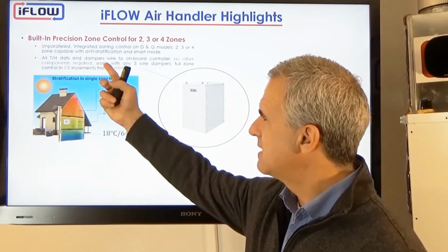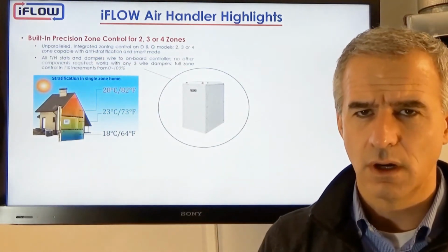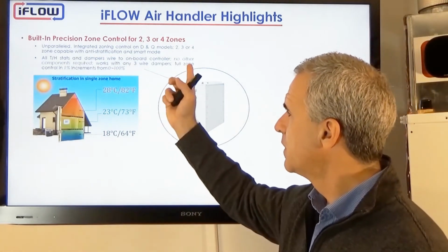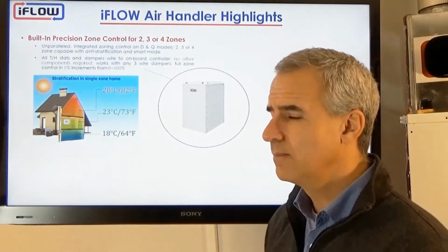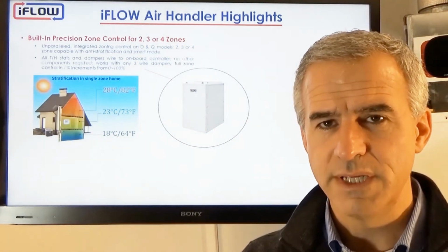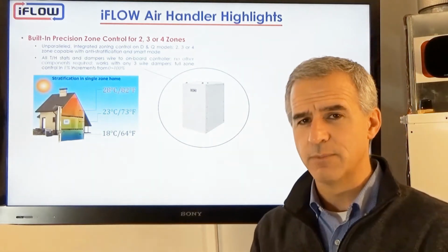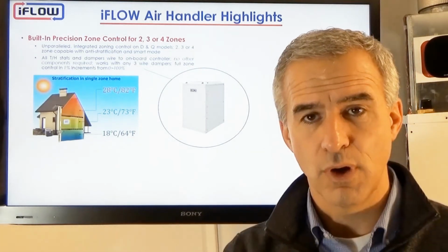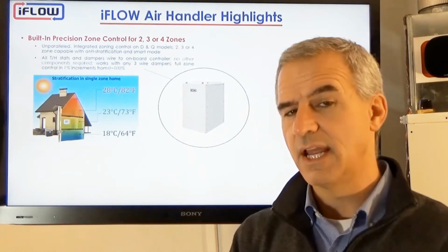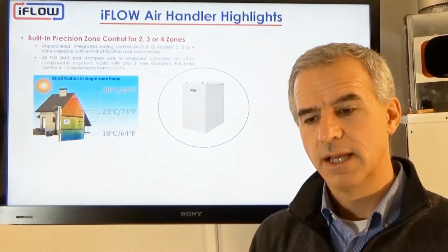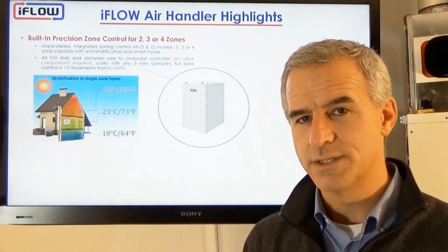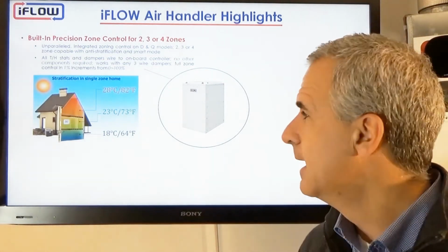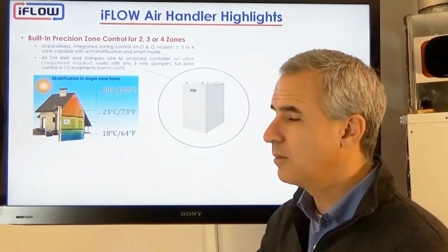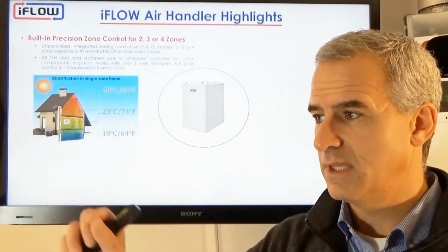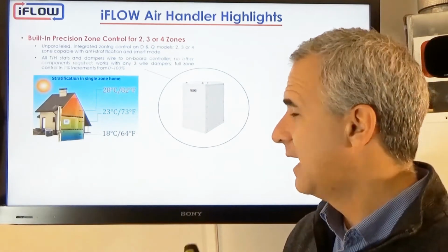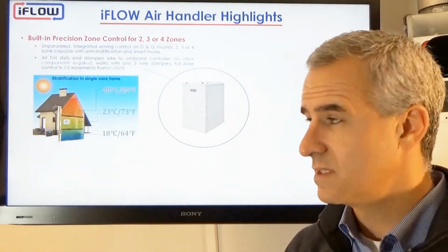All of the thermostats and the dampers will wire directly to our control board, as I showed you a little bit earlier. So there are no other components required. All of our units work with three wire dampers. So we have dampers that go with our product. We have a 6, 7, and 8 inch round, and then we have an 8 by 8, 8 by 16, 8 by 20 square and rectangular. Dampers that can come with our system. If you're using another manufacturer's dampers, then any 3-wire damper will work with our system.